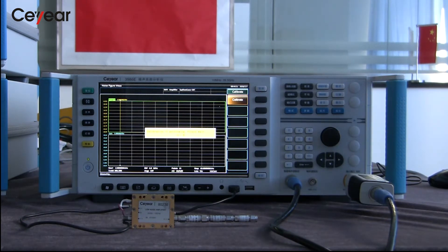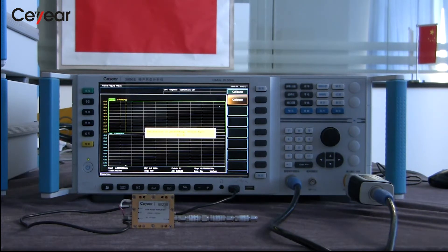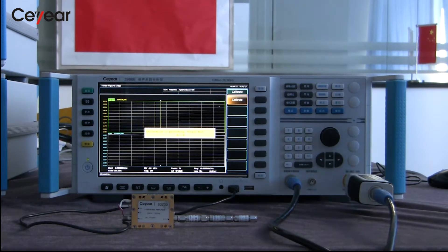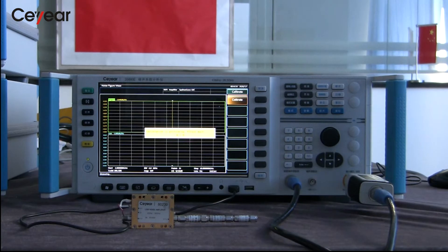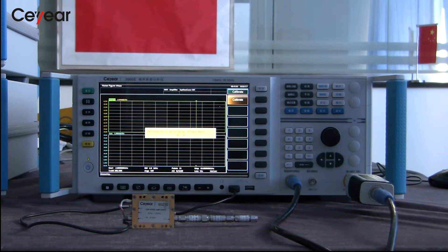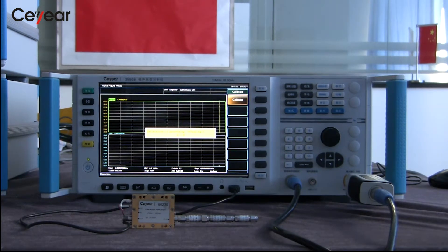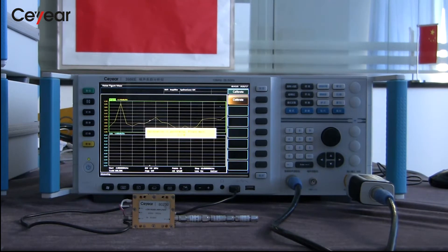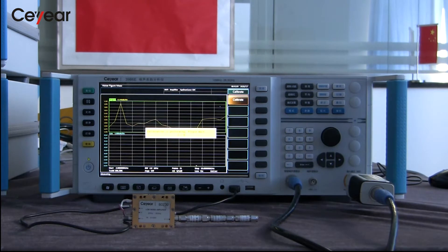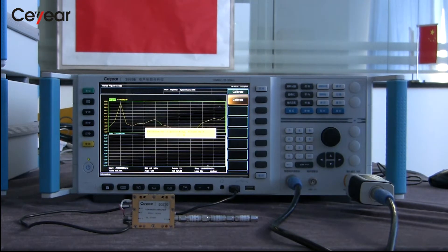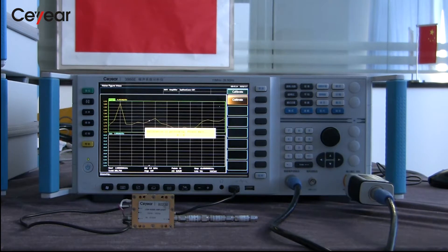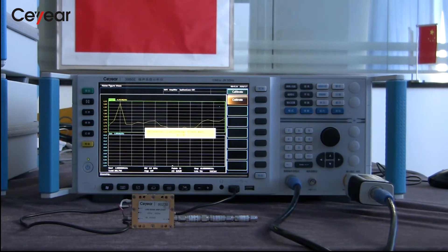The instrument is in calibration process now. There are several combinations of amplifier and attenuator channels inside the noise figure analyzer. The calibration process can measure and save different channels' self-noise. After performing the measurement, the instrument will automatically subtract the instrument's own noise and then get an accurate result.